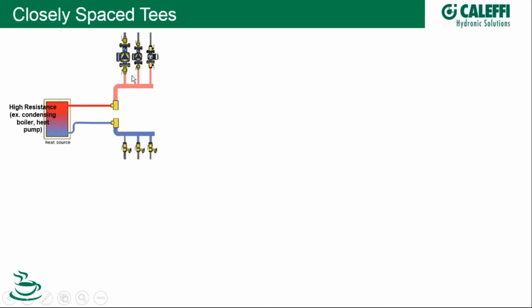Now let's say this first pump kicks in. The first pump sends flow up, comes back around, and comes to the return header. Now we've increased our flow significantly with that pump. Now we can't get all that flow, like we'd like, through the full flow arrangement here. As a result of this bottleneck or restriction, there's going to be back pressure created against these return circuits, these connections here, which means back pressure against each of these 2 pumps.